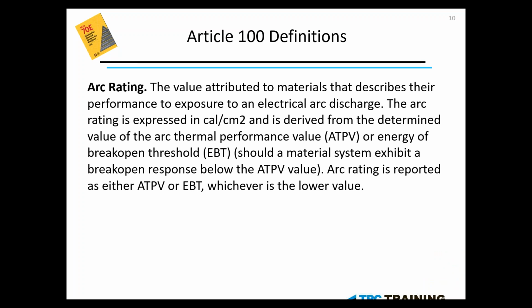The next one is arc rating. Arc rating is the value attributed to materials that describes their performance to exposure to an electrical arc discharge. The arc rating is expressed in calories per centimeter squared and is derived from the determined value of the arc thermal performance value, ATPV, or energy of break open threshold, EBT, should a material system exhibit break open responses below the ATPV value, which is possible from the manufacturers. Arc rating is reported as either ATPV or EBT, whichever would be the lower value.